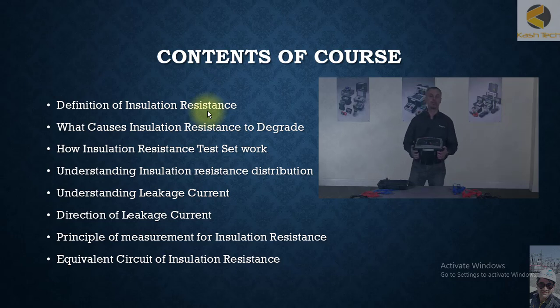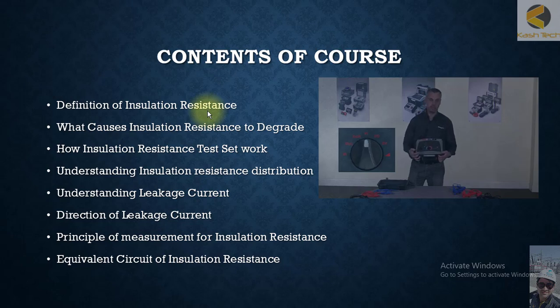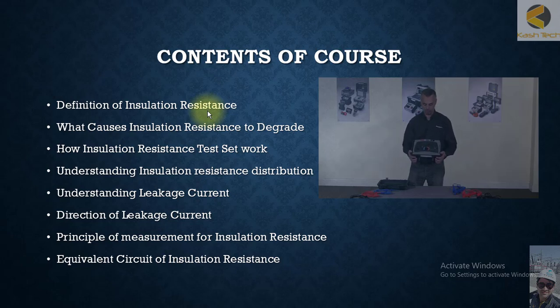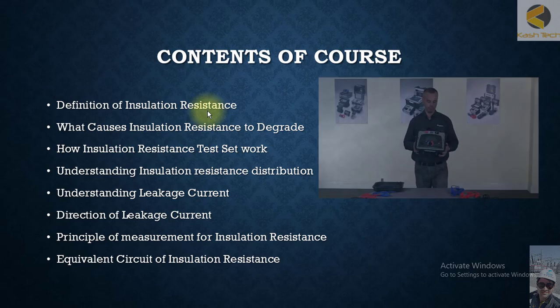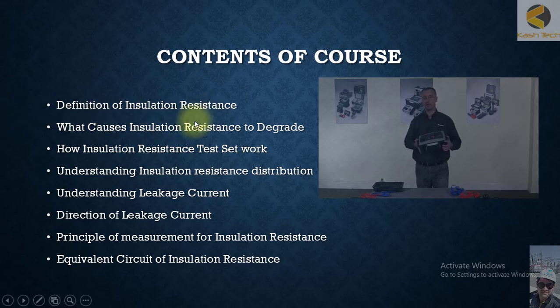Spot testing is done for insulation purposes only. In maintenance, there are other methods where we give some time, measure the reading, and keep a record every year to check whether insulation is decreasing or increasing. This topic is very important whether you belong to a commissioning team, a solution team, or a maintenance team. Insulation testing is also one of the most common interview questions for newcomers.